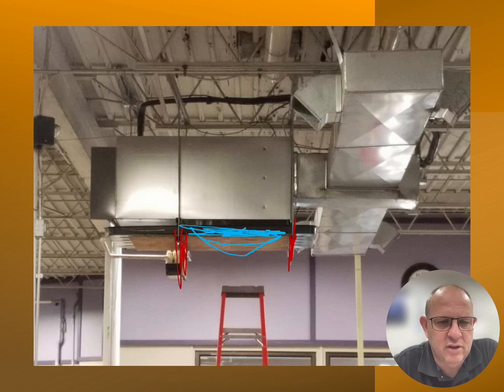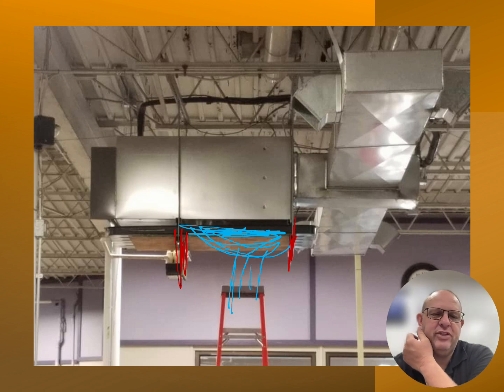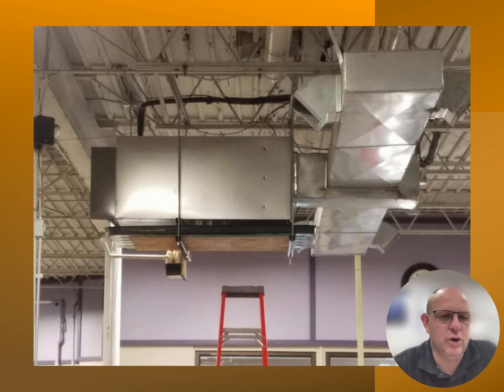So the way to prevent this from happening is to go ahead and put a piece of plywood, like I have done, underneath that pan. It stiffens it up and doesn't let it bow, so that if there is any overflow or drippage from the evaporator coil, it will flow directly back into the condensate pump and will pump that condensate out into the outdoors.